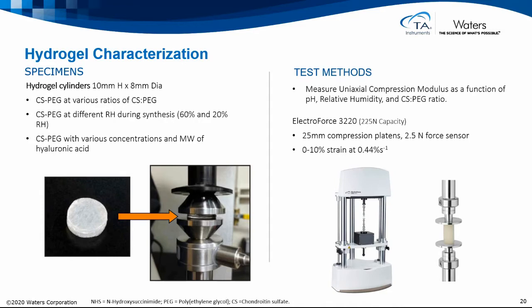From a methodology perspective, they're using one of our ElectroForce 3220 instruments, 225 Newton capacity, and they measure a compression force by applying a compression strain, increasing from 0 to 10% strain at this strain rate. They're doing this between platens, which some people call parallel plates.